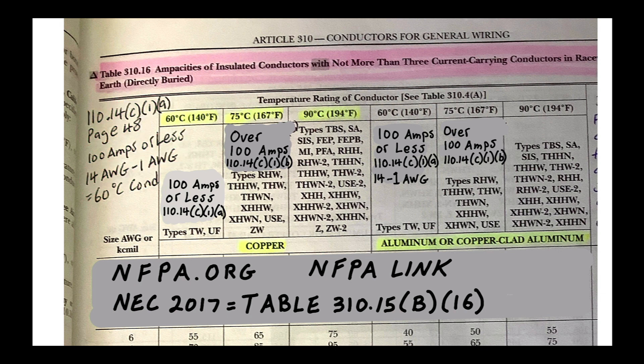Now looking at the 75°C column — and we're talking copper here. If the question doesn't specify conductor material, assume copper unless told otherwise. The 75°C column applies to loads over 100 amps per 110.14(C)(1)(b). If the question specifies aluminum, then use aluminum; otherwise it's copper.